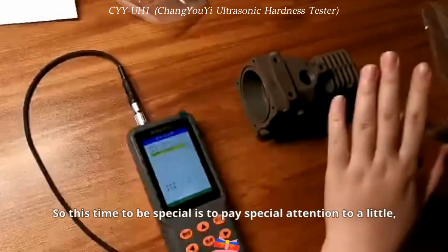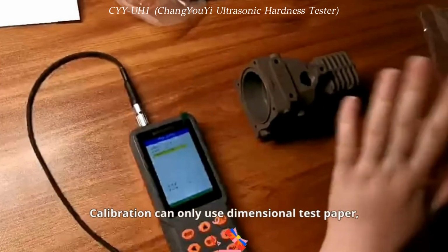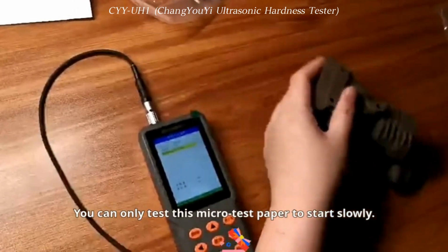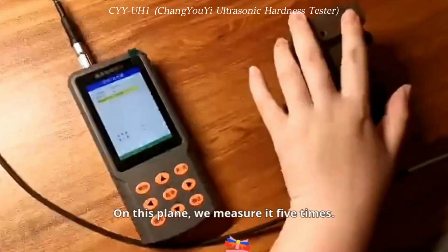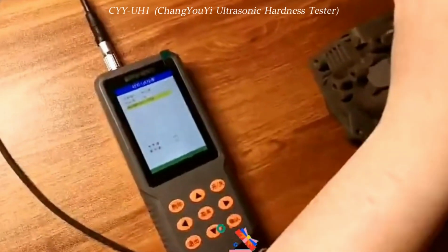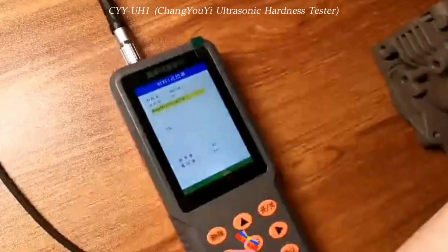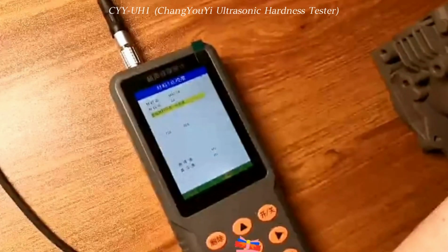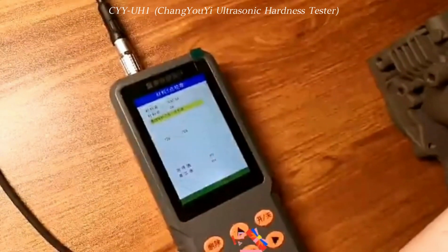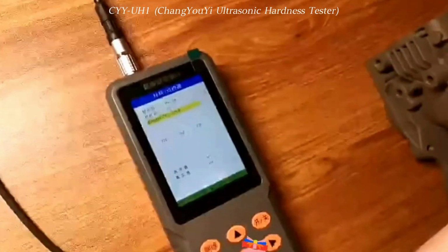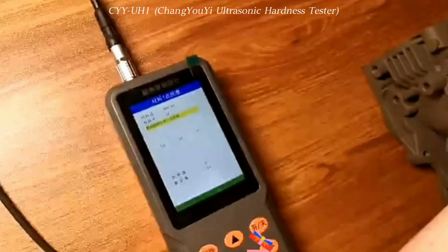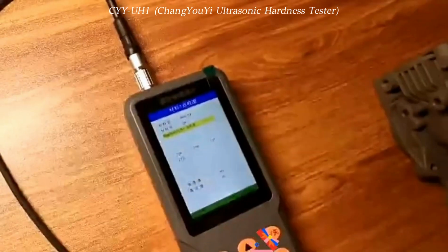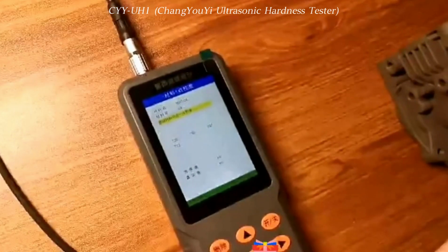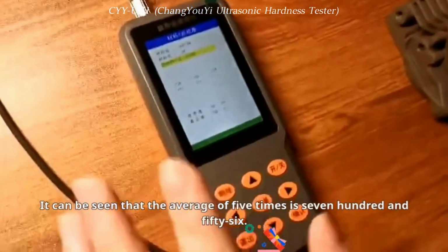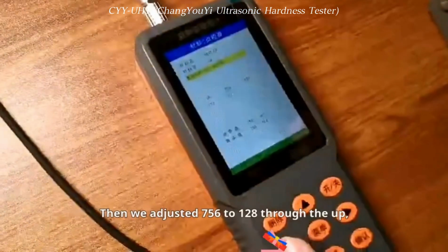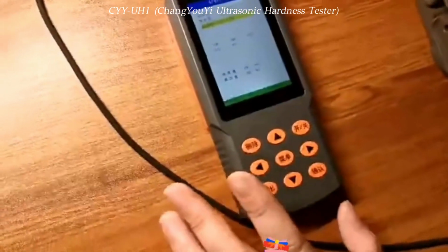So pay special attention: single-point calibration can only use Vickers test values, and you can only test in HV. On this plane, we measure it 5 times. It can be seen that the average of the 5 times is 756. Then we adjust 756 to 128 through the up, down, left and right keys.